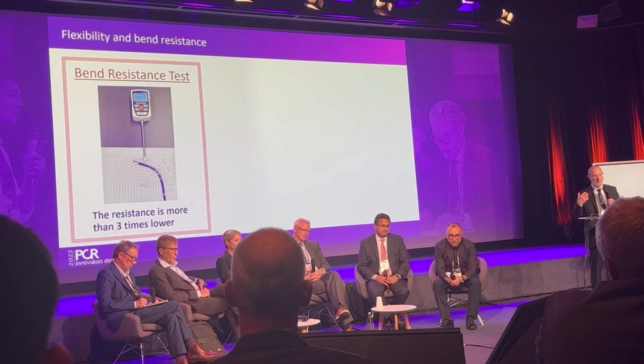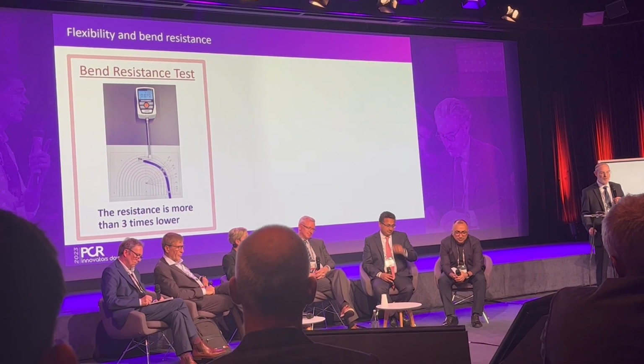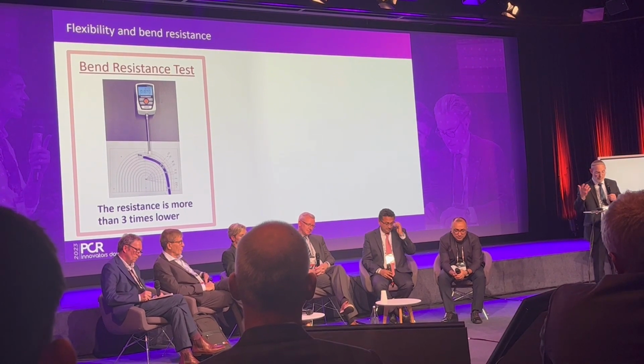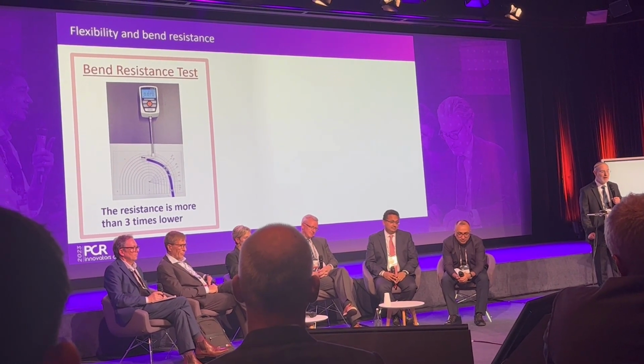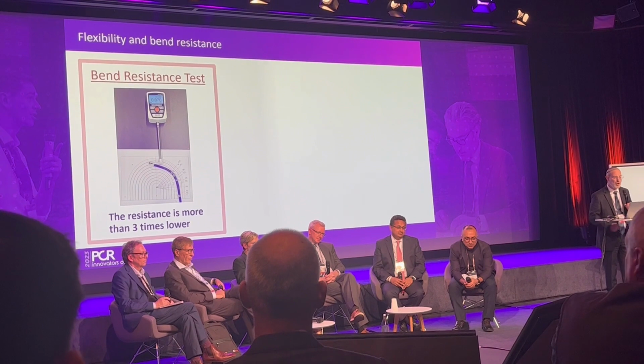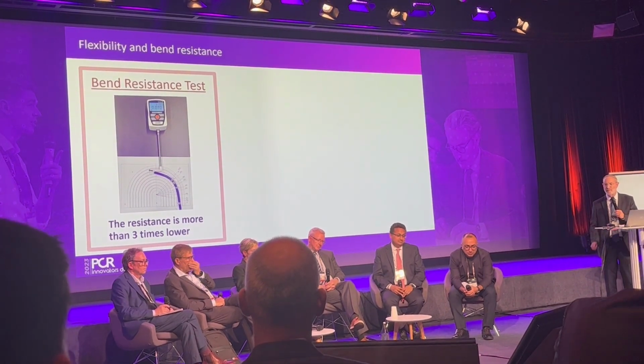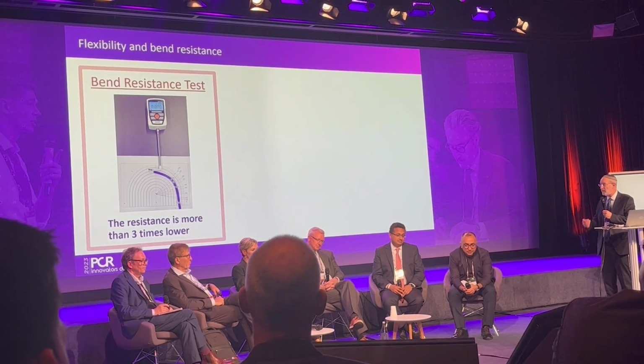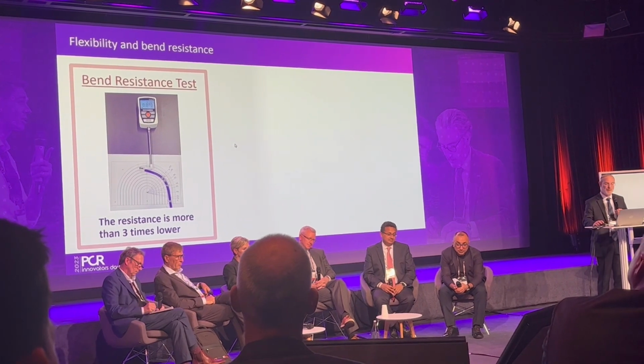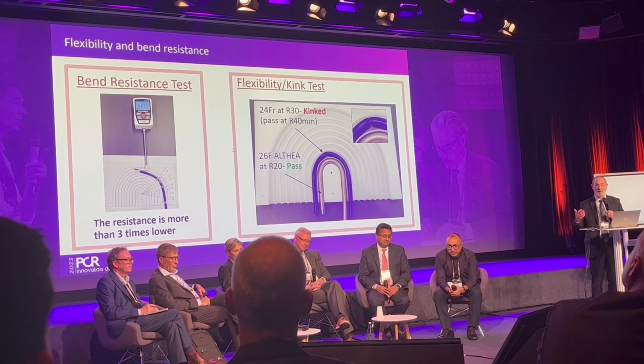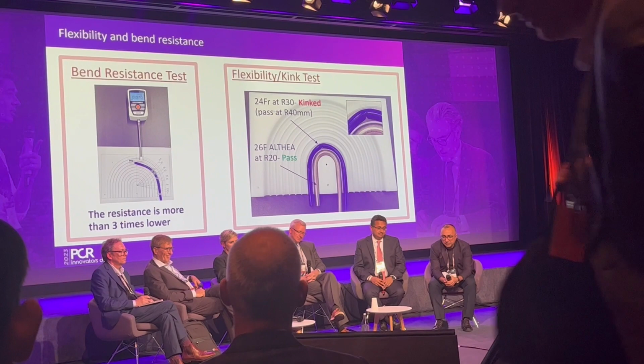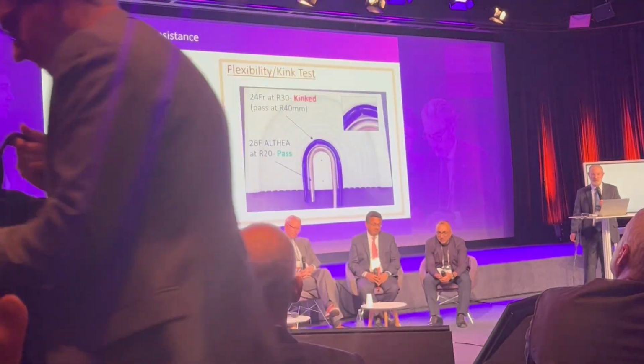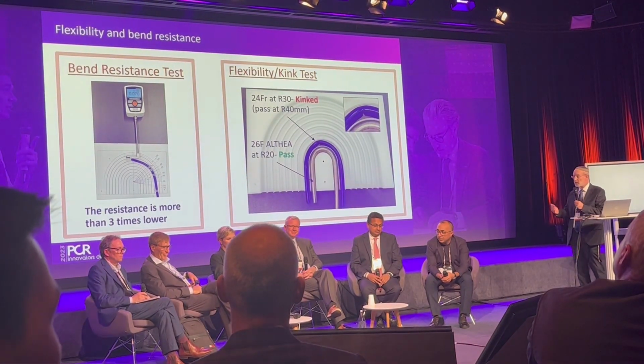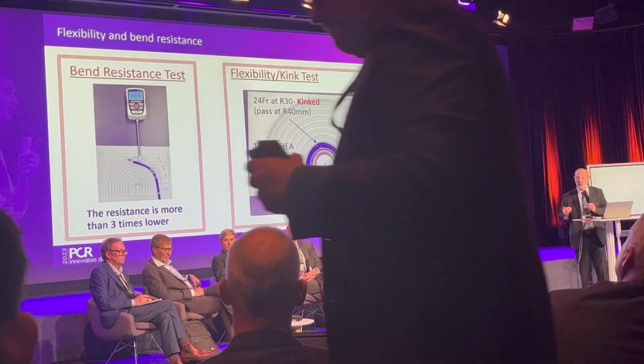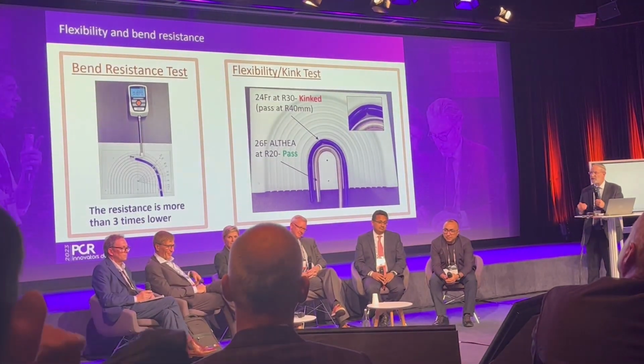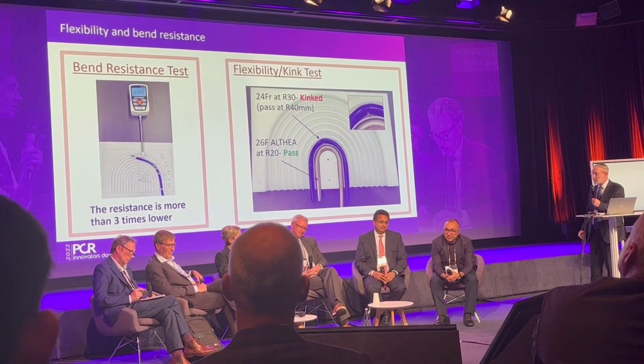When we took this catheter and we compared it to a 24 French commercially available catheter, we assessed the resistance in a sample, and we showed that the resistance of this novel catheter is 3 times lower than the on-market device. Then further, we did a flexibility or kink test, and the 24 French system was able to pass 40 millimeter radius without any trouble. At 30 millimeter, it kinked. The Althea device can go to 20 millimeters without any kink.